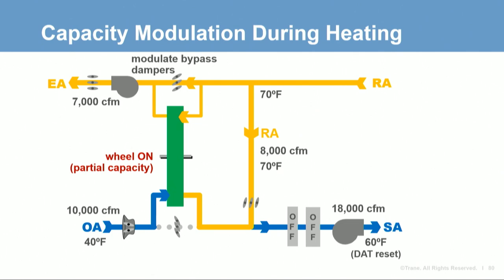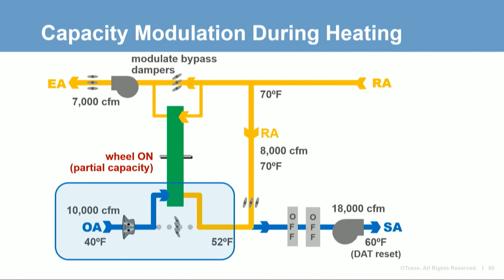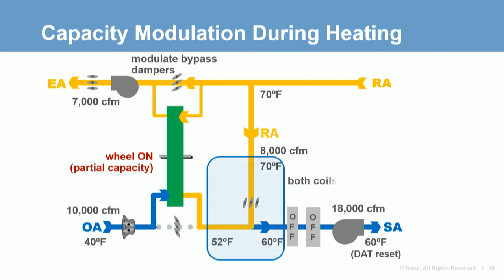With less warm air passing through the exhaust side of the wheel, the outdoor air does not heat up as much, warming to only 52 degrees. The resulting mixed air temperature is now 60 degrees, so neither the cooling coil nor the heating coil need to operate. The approach for modulating capacity differs among the various devices.